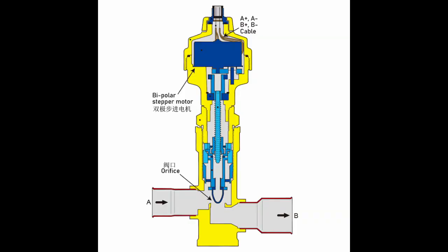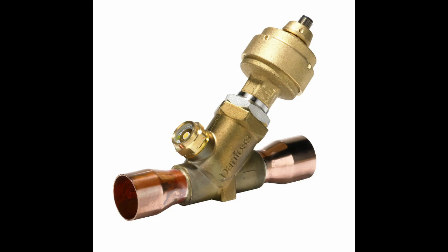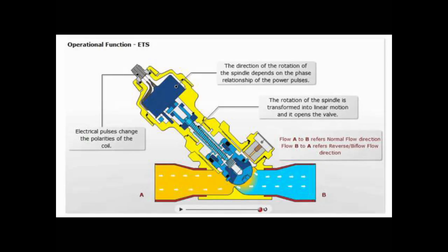Welcome back to UAT Solutions. In this tutorial, we will discuss the electronic expansion valve and superheat. An electronic expansion valve used in refrigeration and air conditioning systems controls the flow of refrigerant into the evaporator. It is an electronically controlled metering device capable of modulating refrigerant flow with high precision based on the actual cooling demand of the system.